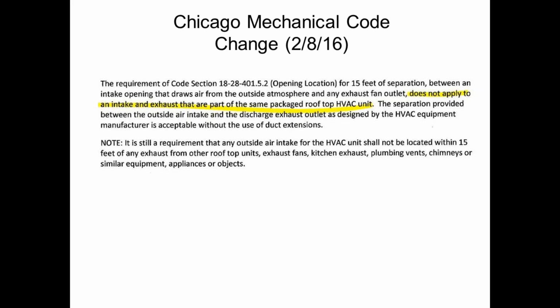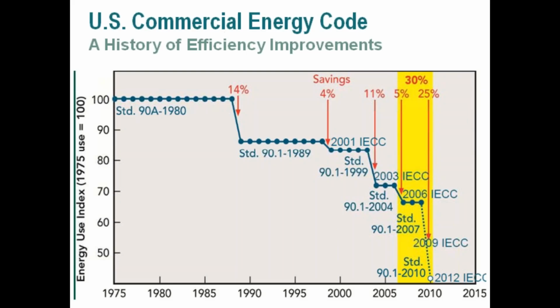Now, if there's some other exhaust source from the building, like toilet exhaust or some other combustion exhaust that's unrelated to the rooftop that's near your rooftop intake, you would still have to do it in that case. But the rooftop itself, you don't have to be 15 feet away from itself anymore. So that may help some of you guys with some of your labor and effort on the roofs there.